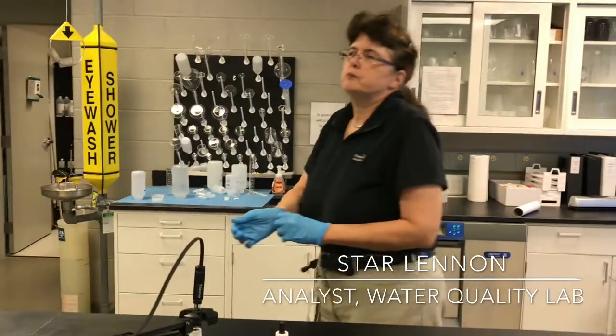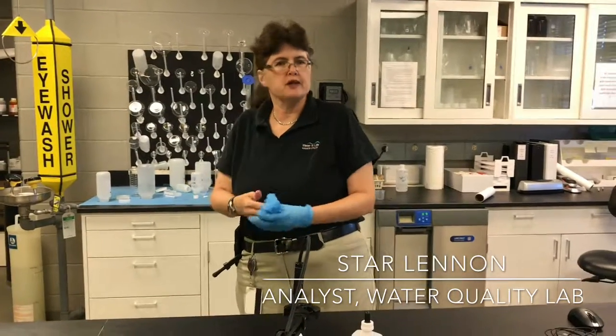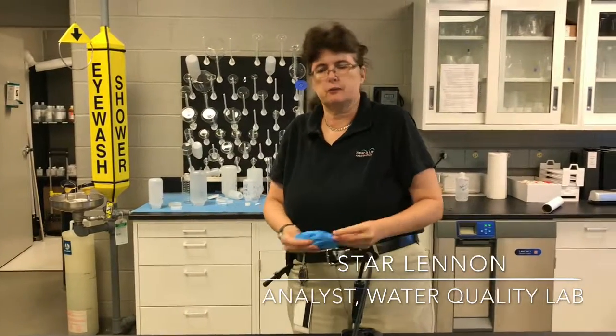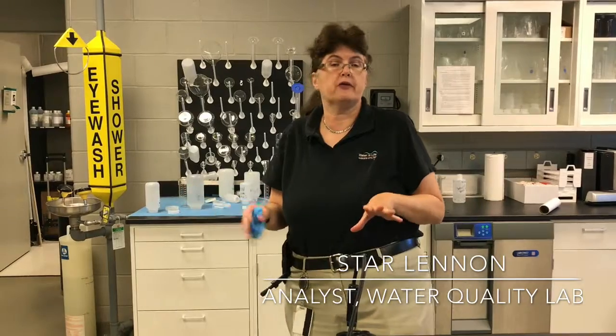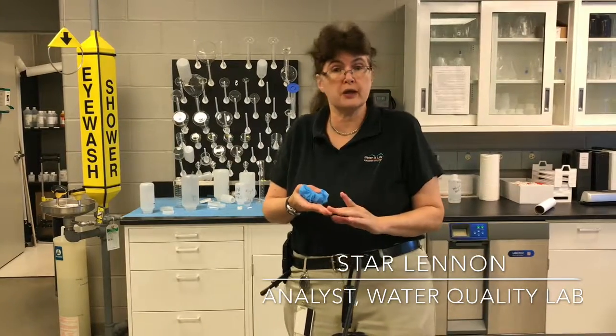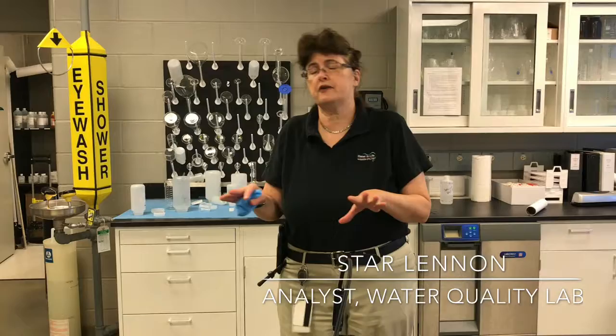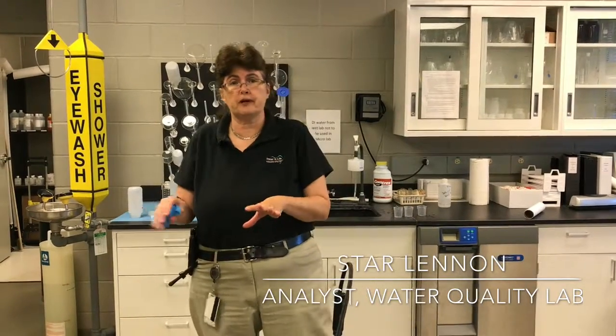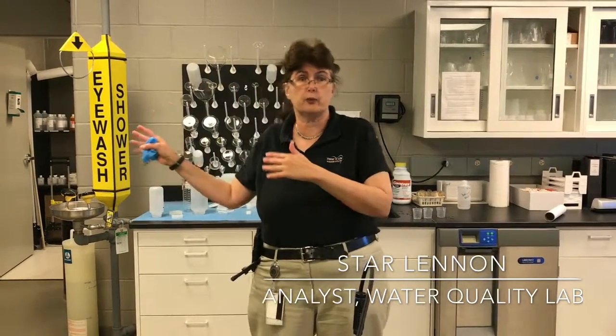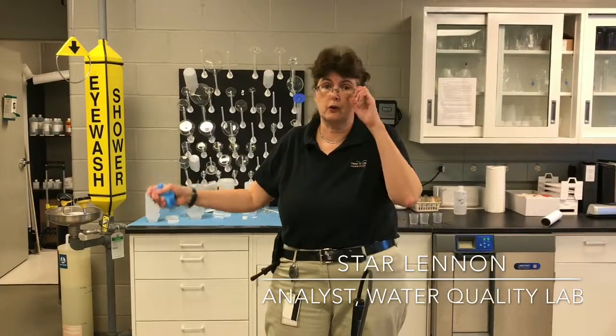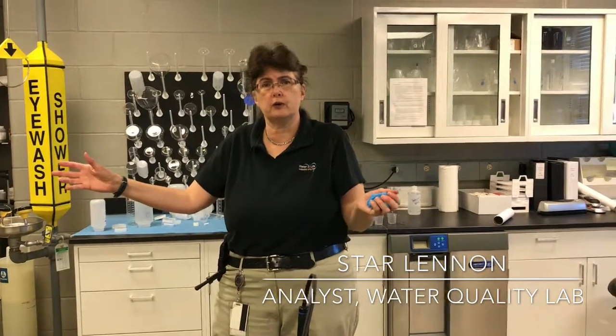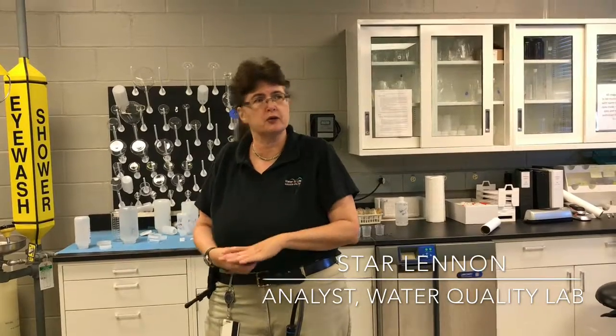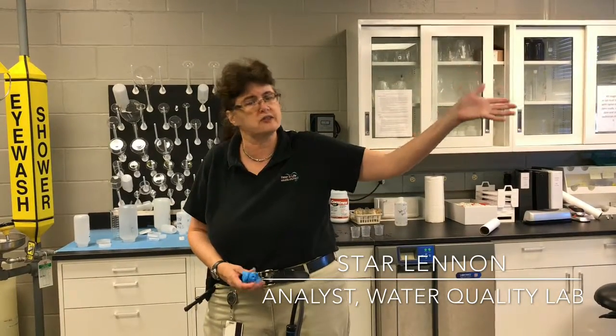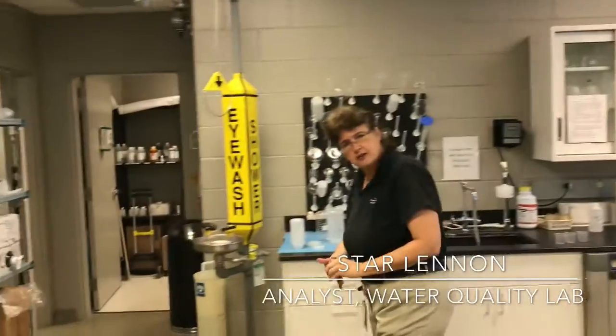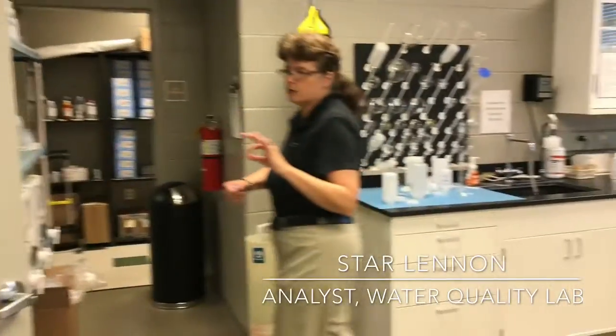The other thing we do, more in line with the EPD, is microbiology testing. We have 120 sites every month that we pull for bacteria testing, pH, and chlorine testing. It's one thing to make the water and know it's safe here at the plant, but we also have to verify that it's safe when it gets out to the public. So we test down to Sandbar Ferry Road, down below Hephzibah McBean, all the way out Washington Road and Stevens Creek. We have some bacteria in the incubator right now, so they have to be grown at a very specific temperature.